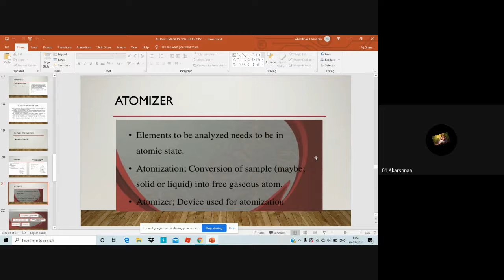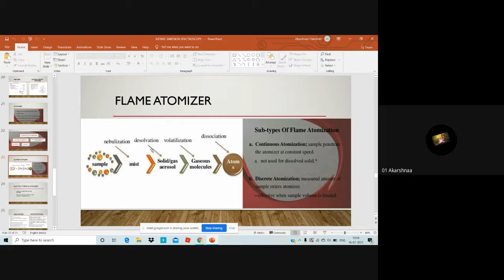In continuous atomization, the sample enters the atomizer at a constant speed, and it is not used for dissolved solids. In discrete atomization, a measured amount of sample enters the atomizer, which is effective when the sample volume is limited. If sample volume is limited, discrete atomization can be used. The process involves nebulization, desolvation, volatilization, and dissociation.